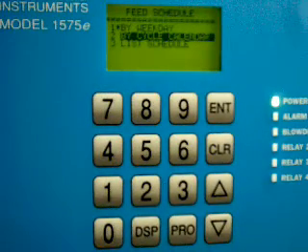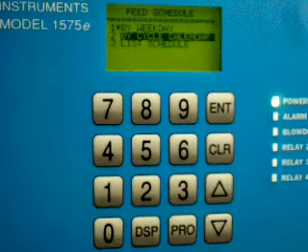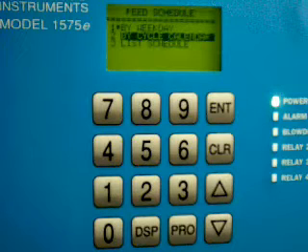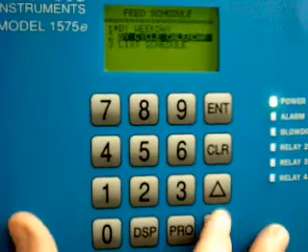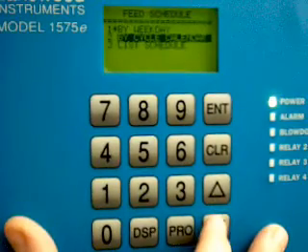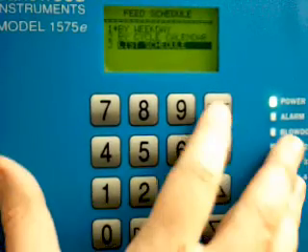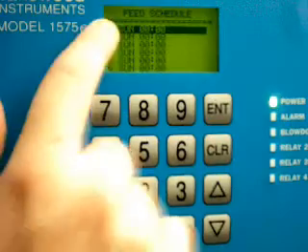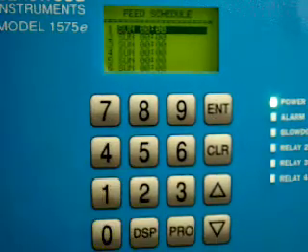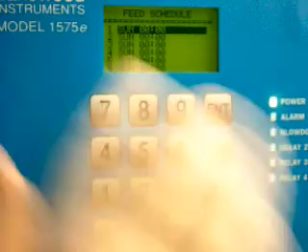This is currently set up by weekday. So as I look at the schedule, when I start scheduling the days to use, it'll be Monday, Tuesday, Wednesday, Thursday, instead of day one, two, three, or four, or five of a particular day schedule. So now I'm going to go down to the list of the schedule. I'll hit enter. The first item in my list is the first control scheme in my list, so I would go ahead and hit enter through this.